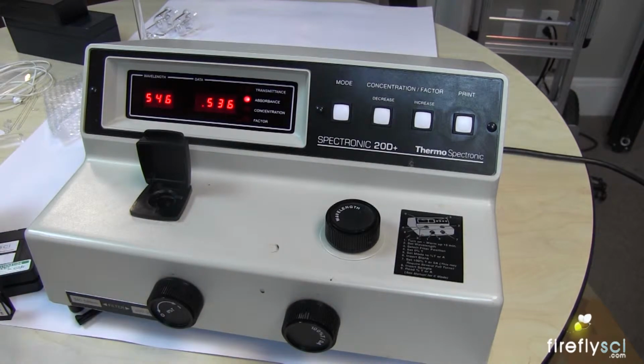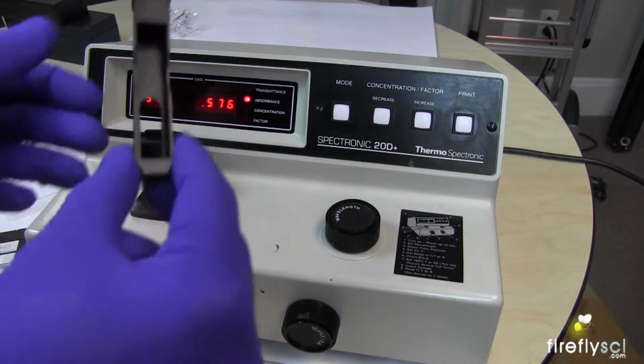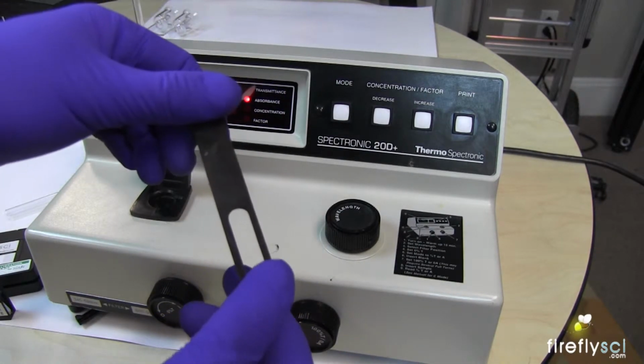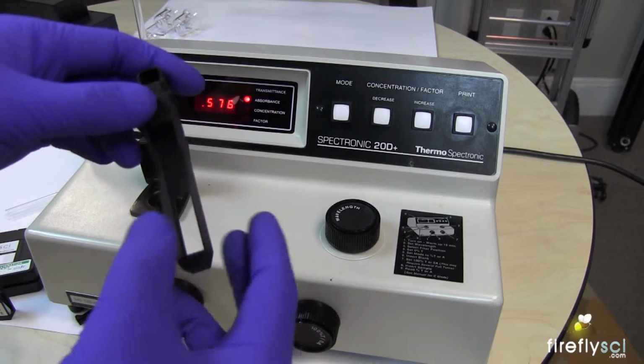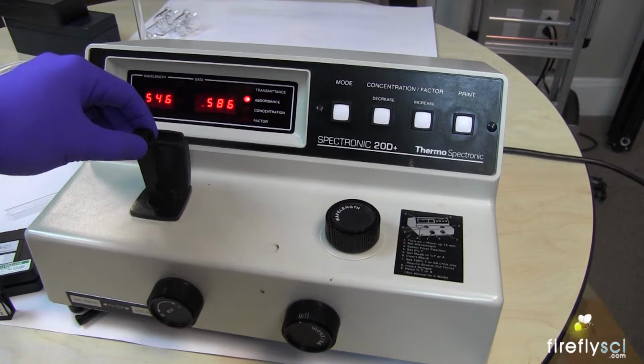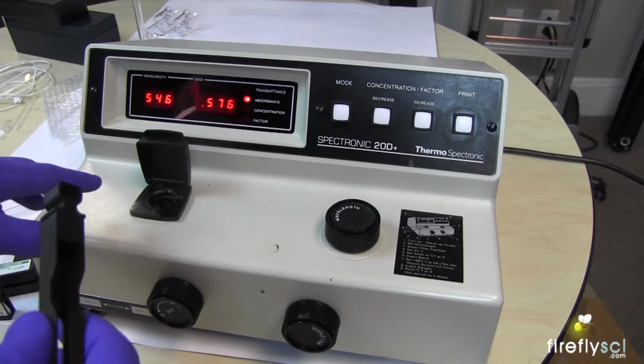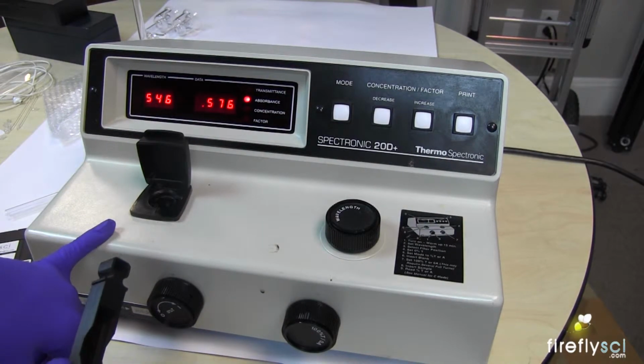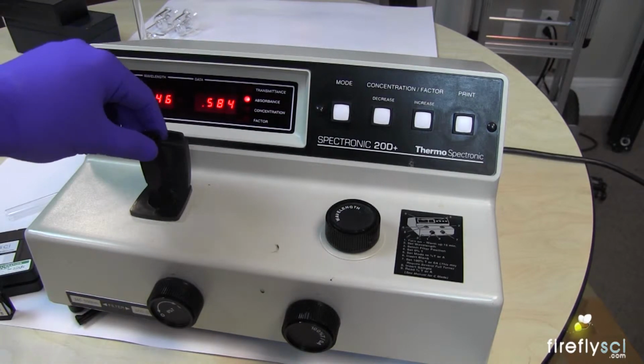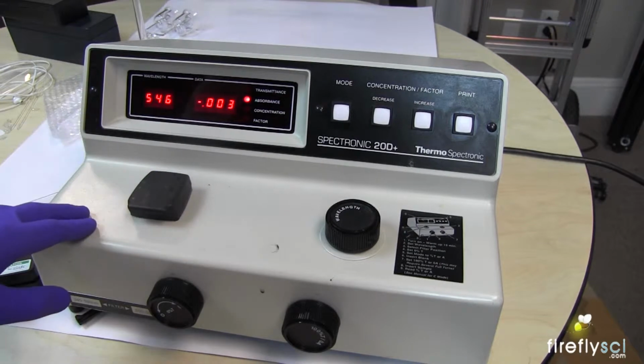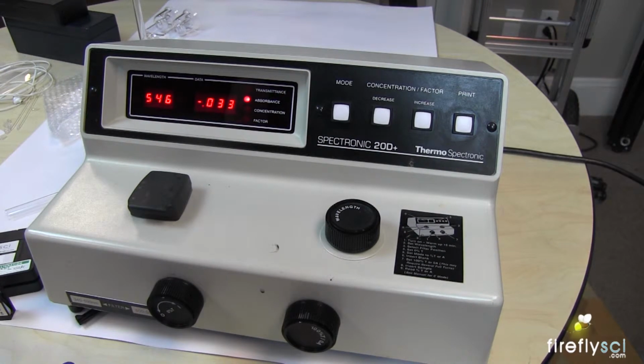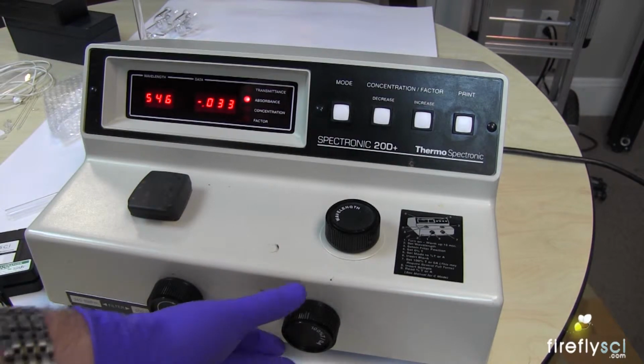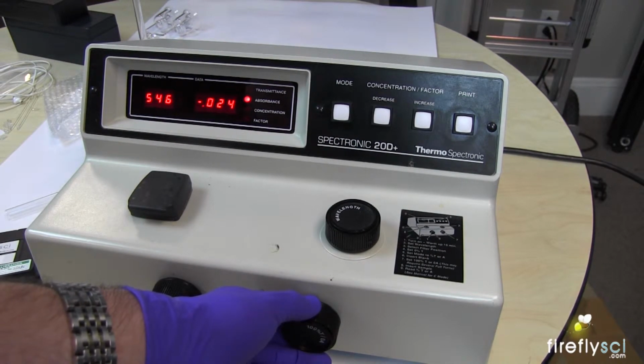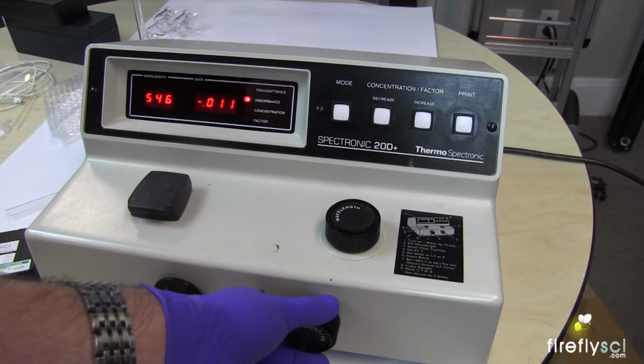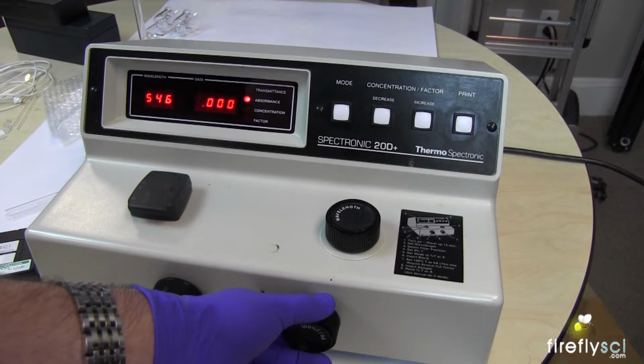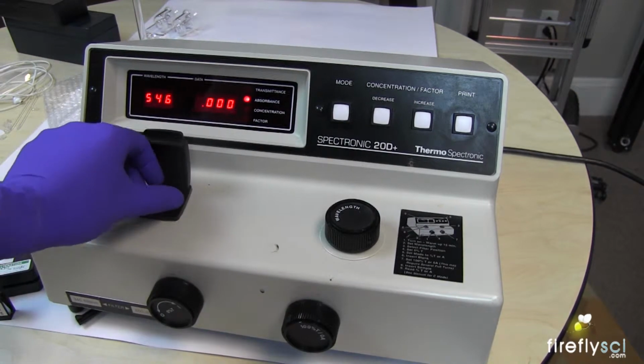So what you have to do if you have these machines is get one of these holders. This holder is awesome because it allows you to put a standard cuvette way down into this machine, and you can also pull it back out. Another note about this machine is that you need something in this holder; there must be some kind of mechanism in the bottom that engages when you put something in, and then you can zero the machine. You cannot zero this machine without something being all the way down in the bottom of the cuvette holder. So I'm going to go ahead and zero it out now. There we go. Take out our holder.